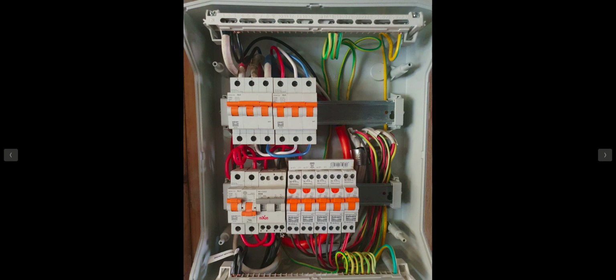Obviously, if I switch this to grid, the neutral to these backup circuits will be connected to the main neutral. So in backup mode, the neutral coming out the top into these circuits will be connected to the output from the Solis.